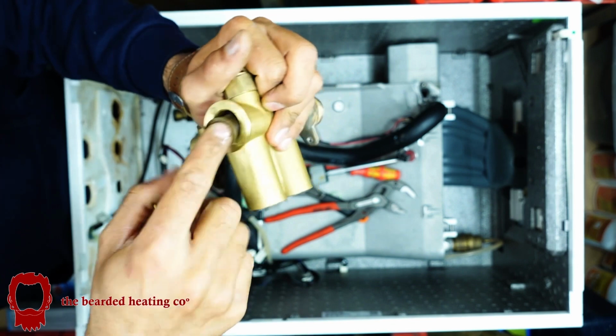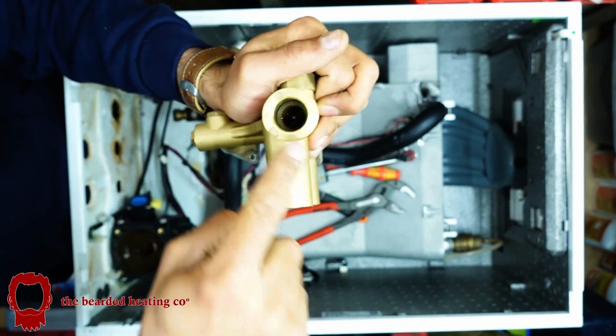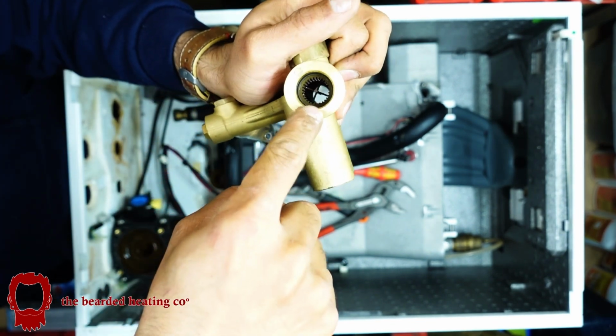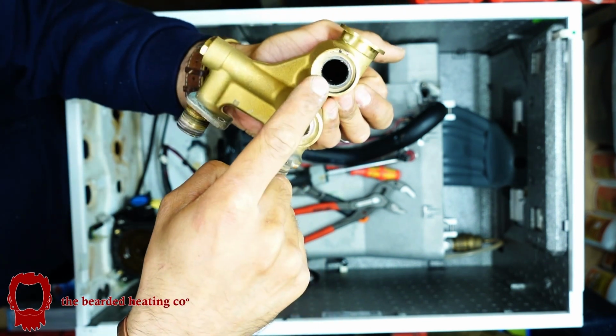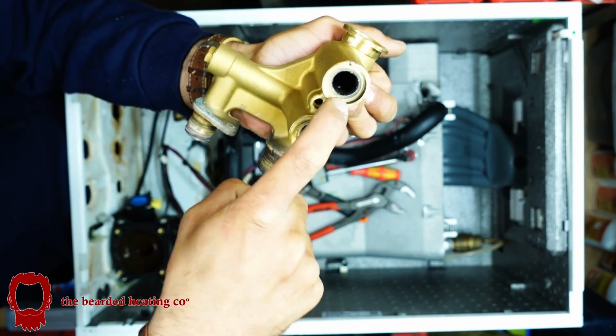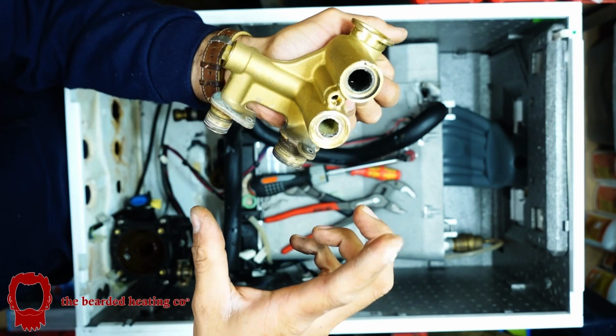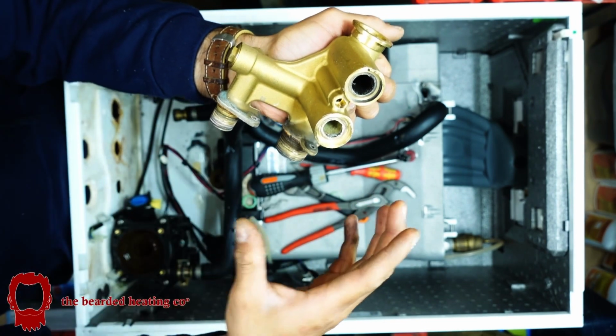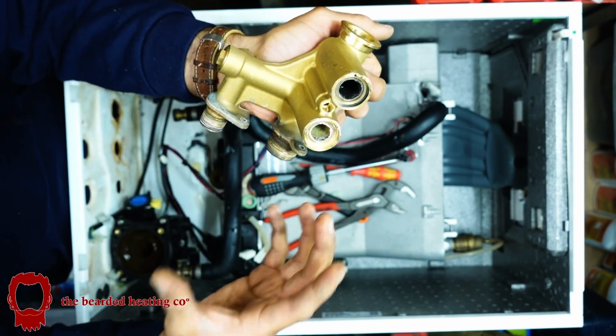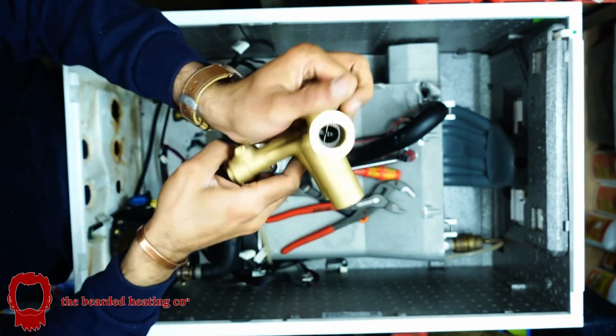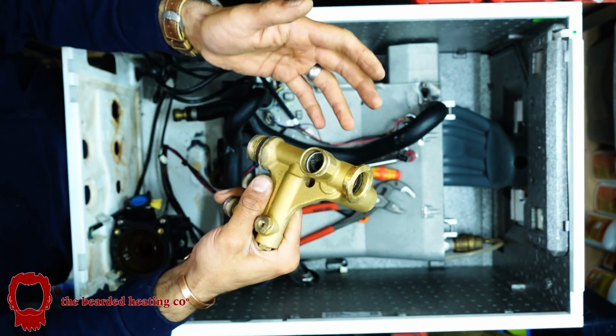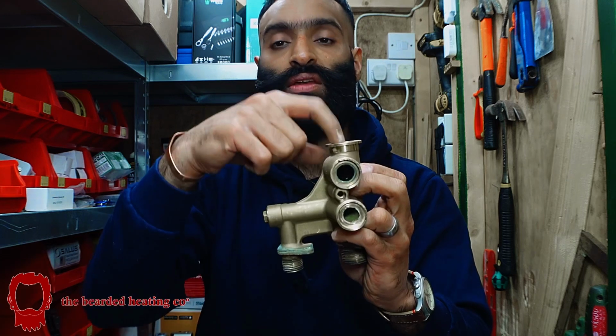So if I put the filter back in, water goes in this direction, and the reason that filter is there is because it's protecting this outlet, because this outlet goes to the plate heat exchanger, and we want to prevent the plate heat exchanger blocking up with muck and debris, which will, in the long run, give you problems with your hot water performance, and that is why you have that gauze filter sitting there.